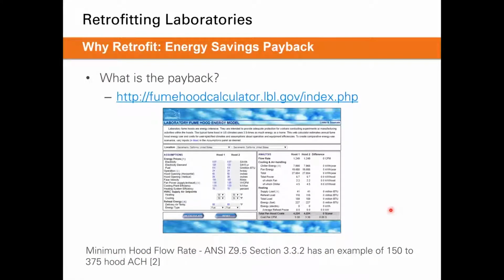So I presented the energy savings that can be afforded by doing a retrofit project and by switching from a constant volume hood to a VAV solution. And the natural next question would be, what is the payback, or how can I calculate the payback for this type of project? There's actually a nice tool that Berkeley Labs has put together where it takes your different variables such as your geographical location and it makes assumptions about energy prices. You can put in different parameters for your hood dimensions as well as hours of operation. And it calculates a flow rate for the hood, as well as the total cost to run that hood per year and the cost per CFM.